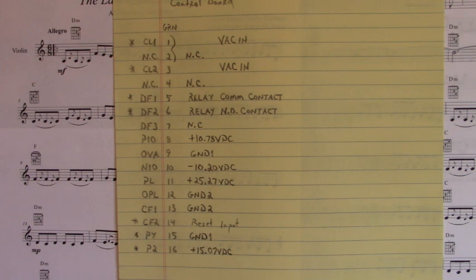And I stopped because I did not want to destroy that circuit by increasing the voltage up to 380, 460 volts AC single phase on 1 and 3. I got scared. I said, okay, we're powered up. I'm stopping right there. Now, in all actuality, you could probably apply 380 volts AC, single phase on 1 and 3, because the front panel said the AC voltage into this drive, L1, L2, and L3, was 400/460.